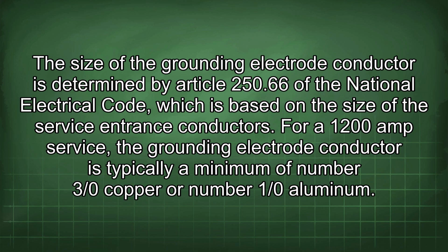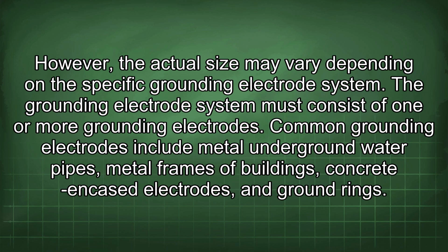The size of the grounding electrode conductor is determined by Article 250.66 of the National Electrical Code, which is based on the size of the service entrance conductors. For a 1200 amp service, the grounding electrode conductor is typically a minimum of number 3/0 copper or number 1/0 aluminum. However, the actual size may vary depending on the specific grounding electrode system.